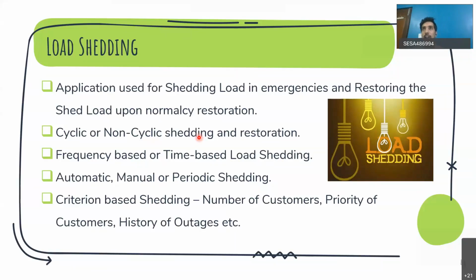There are options to do cyclic or non-cyclic shedding. You can rotate the shedding—shed a particular feeder, restore it after some time, go to the next feeder, restore it, and so on in a cyclic fashion—or shed all feeders at a time and restore all of them at once. You also have options for frequency-based or time-based shedding, so you can set a frequency limit, say 49.8 or something.